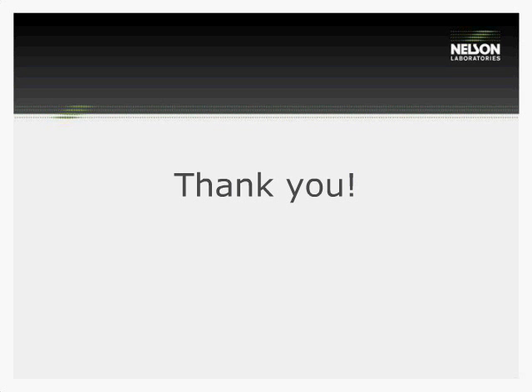Okay, great. Thanks. Our next question is, have you had experience where a device has received approval using the extractables, leachables, and risk assessment to not perform some checkbox tests, such as the standard tests like irritation, for example? Yeah, we have had lots of experience where we use the chemical characterization data to justify out of, for example, chronic toxicity, mouse micronucleus, and even where you can justify out of successfully, even subchronic, subacute, depending on some of the other information we had. And then we specifically use it for justifying out of testing when there are changes to a device.